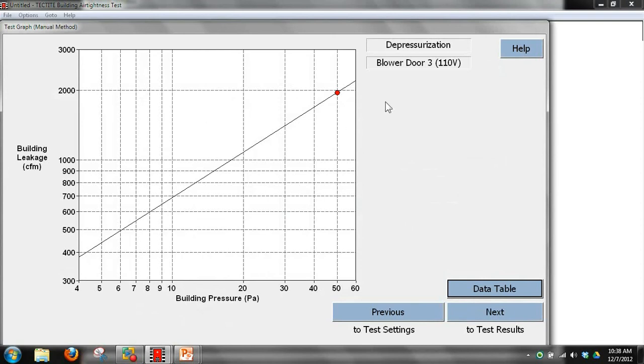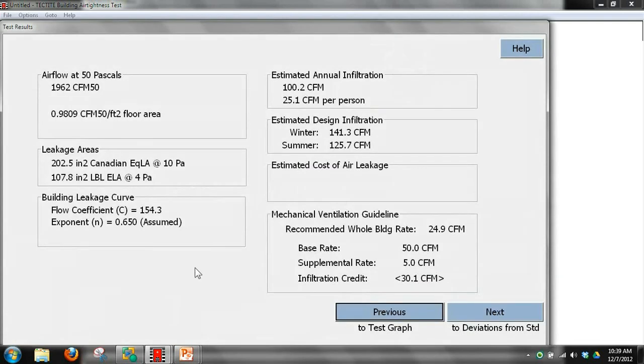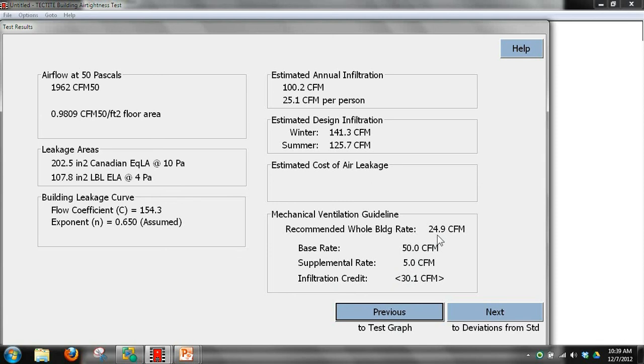Now we're at our test graph page, and it plotted that one data point based on the information we entered. On the next screen, it's showing our CFM at 50 and has calculated our mechanical ventilation information. We've got a base rate of 50, and it figured our infiltration credit at 30 because we have a fairly leaky house for its size. Subtracting 30.1 from 50, our recommended whole building ventilation is 24.9 CFM.